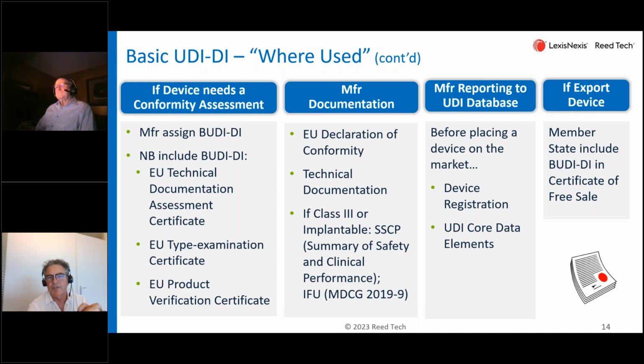But you must start doing that. Start grouping your device, because then you know the structure for your technical documentation and everything from there. So how you can present your device to a notified body and show the evidence of compliance.